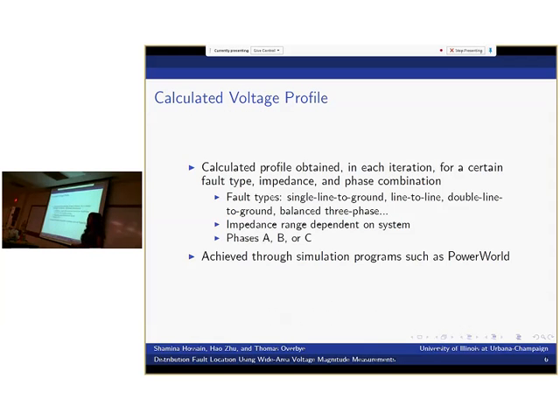And so once we have that measured profile, for each iteration we need to obtain the calculated voltage profile. This profile is obtained through a simulation program, such as PowerWorld, which is what we use for this paper, and obtained for a certain fault type, so single line to ground, line to line, three-phase, and so forth, and of course in phases A, B, or C. And the impedance range would depend on the system that you're looking at. For the 13-bus feeder system, we would have a total of 156 different combinations of fault phase, fault type, and fault location. But for our algorithm, we're assuming that we're given the fault type and the fault phase, so it greatly reduces the amount of simulations that we would actually have to go through to check which one is the best match.